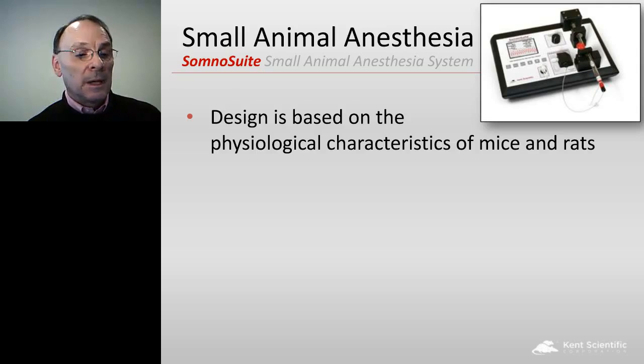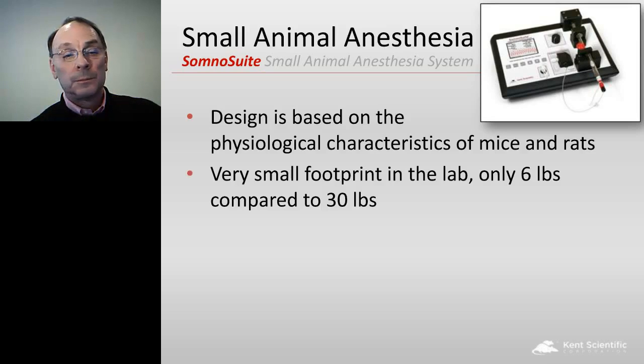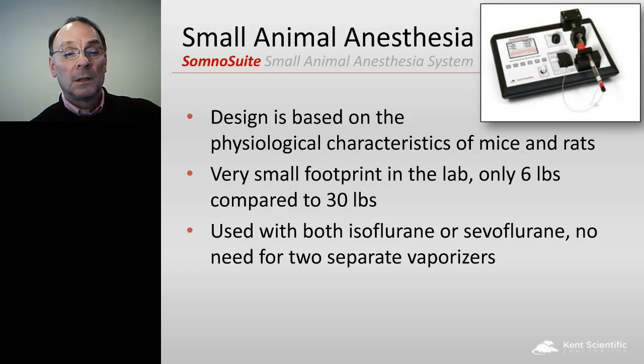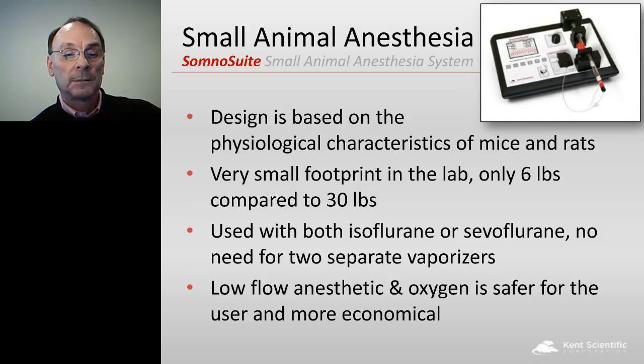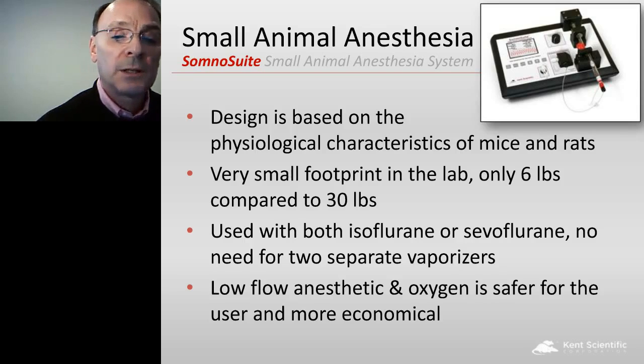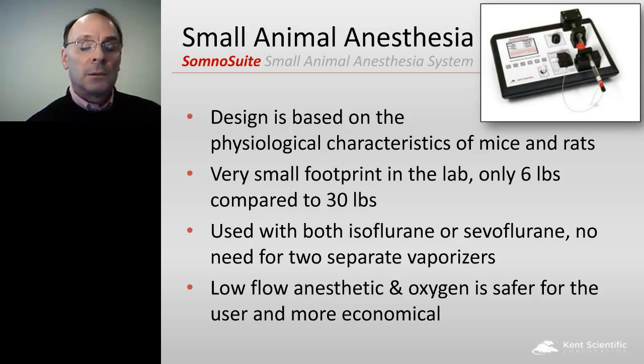The Somno Suite design is based on the physiological characteristics of rats and mice. The small footprint is 6 pounds or less compared to 30 pounds. The same unit can use either isoflurane or sevoflurane, or if there's another gas or liquid anesthetic, all we need to know is the molecular weight, and we can put it into the program and use that. It requires low flow and low oxygen use and is safer for the user.